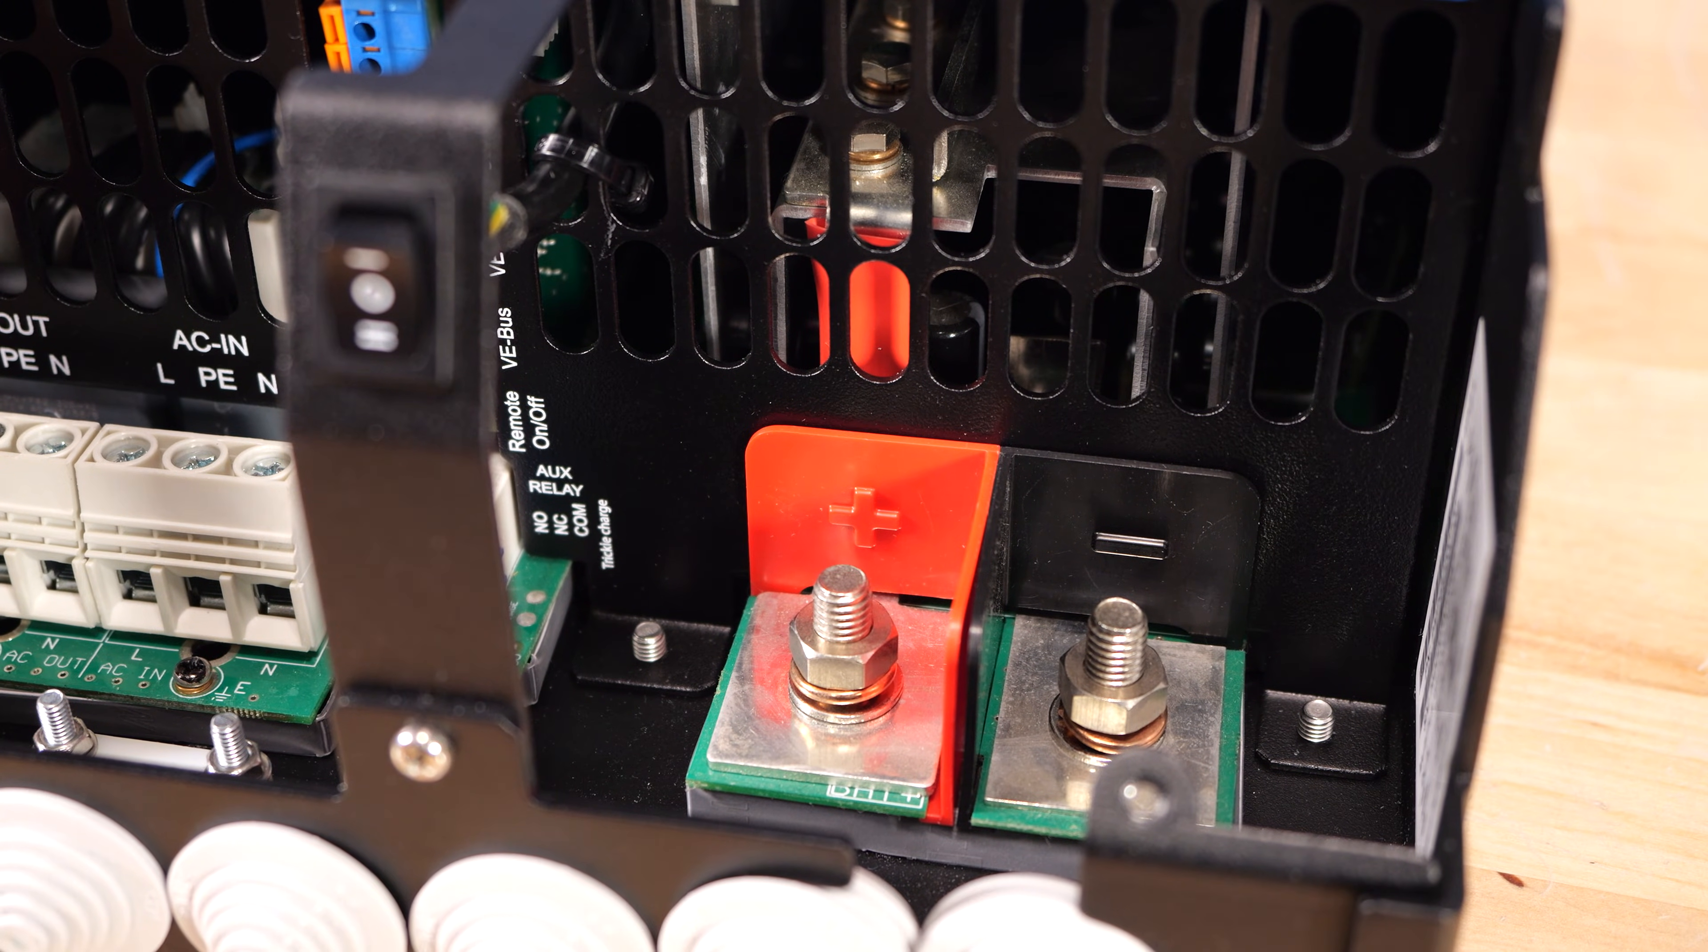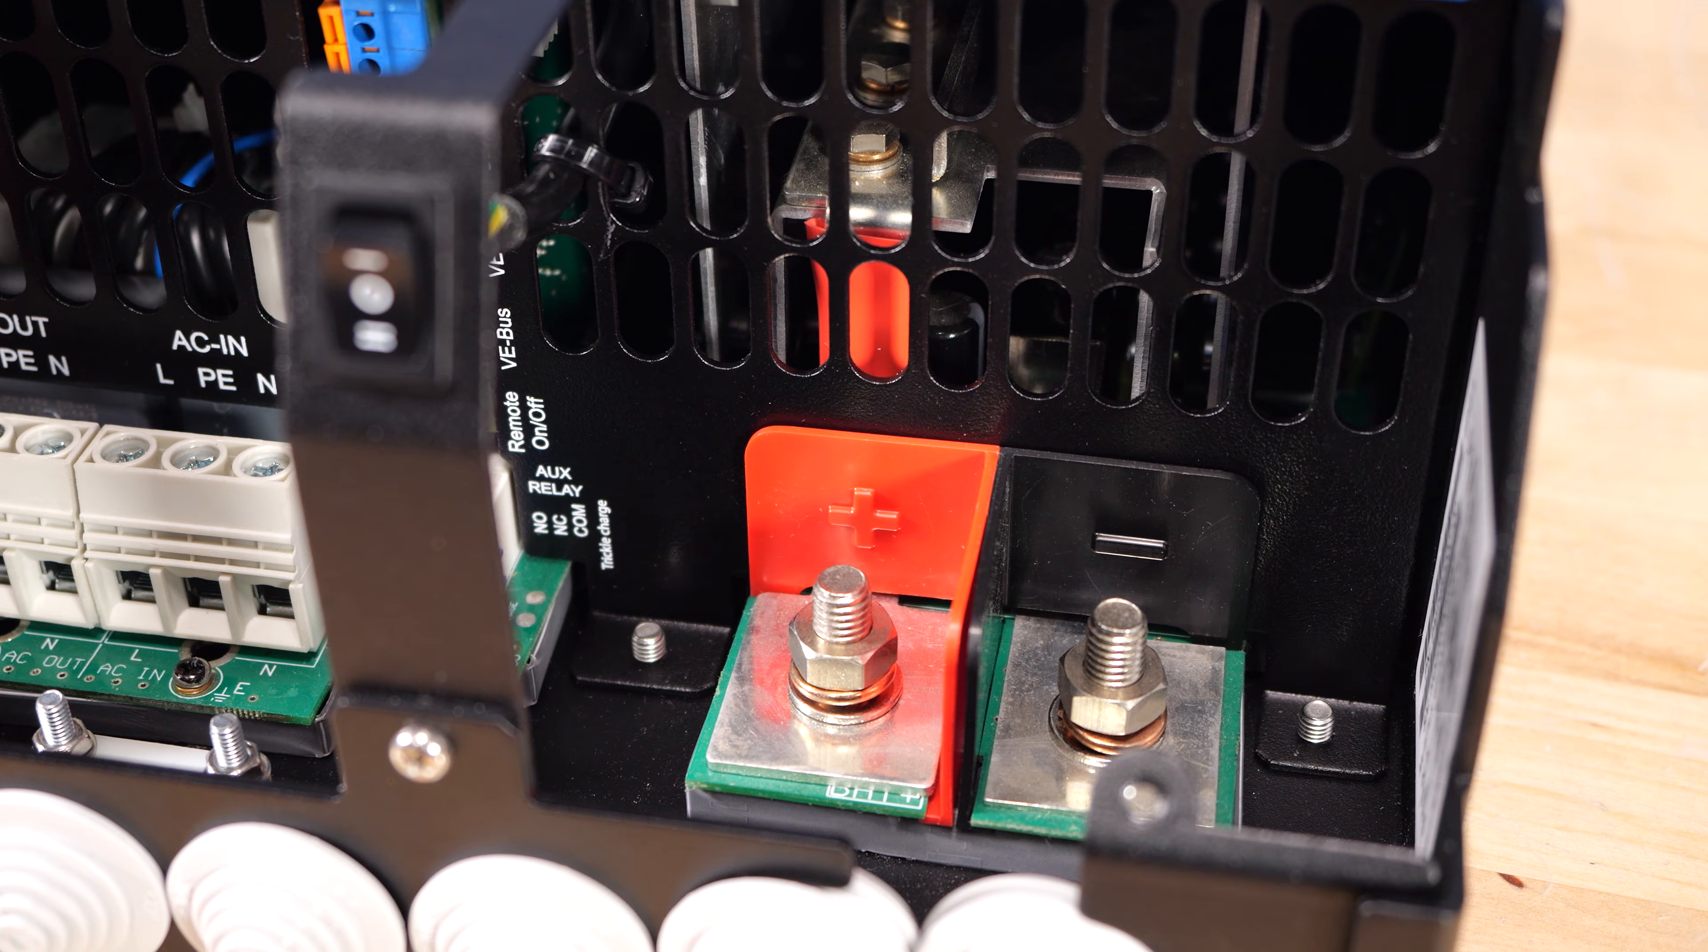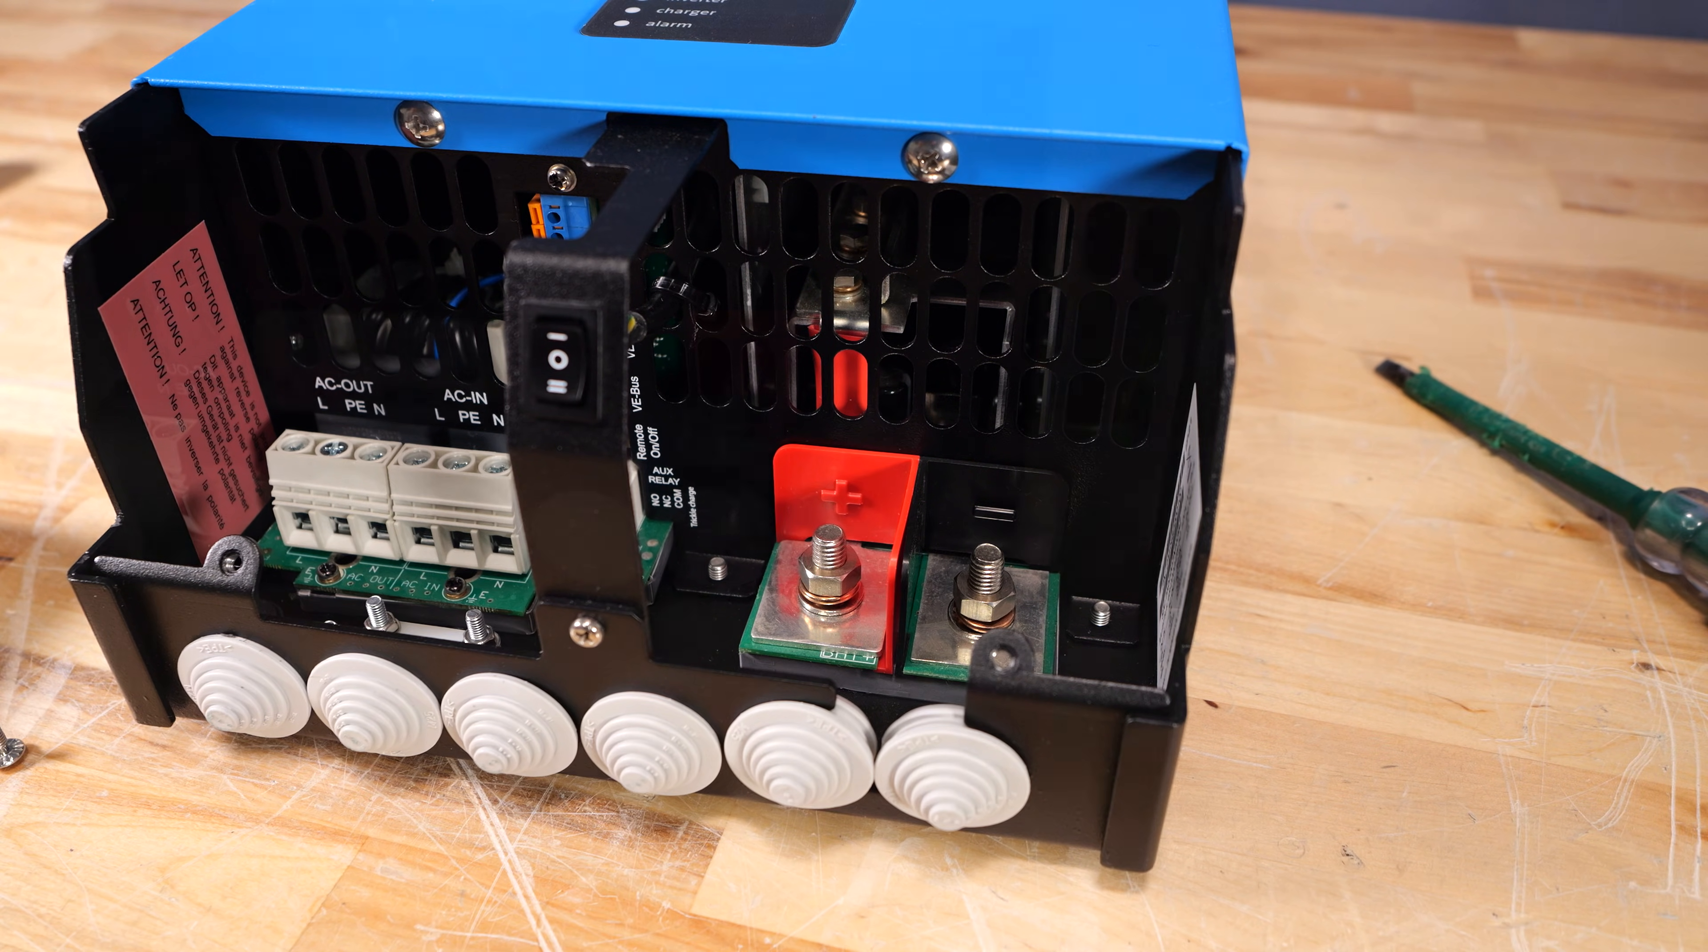Then on our other side of the wiring compartment, we have our positive and negative battery terminal connections. These inverters can take a wide range of battery voltage, as low as 38 volts and up to 66 volts. That makes it a great choice if you're using various different battery chemistries, including nickel-cobalt-based chemistries that have very odd voltage profiles. The torque spec on these DC terminals is 106 inch-pounds or 8.8 foot-pounds. You'll want to make sure you use a torque wrench when you're dialing this stuff in, because that torque is pretty critical.